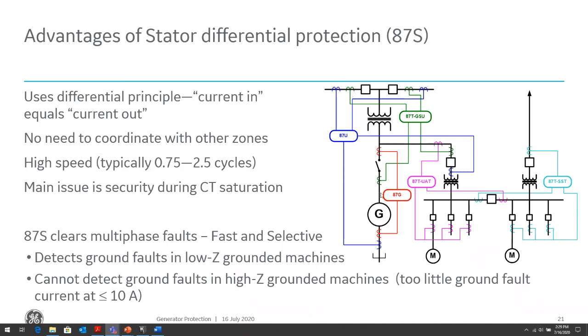For faults within the generator zone, the currents are entering, again, the neutral CTs of the generator and entering the terminal CTs of the generator. So now they add vectorially and you will see a high differential current, and we will use that principle to trip the generator immediately for phase faults within the generator zone.